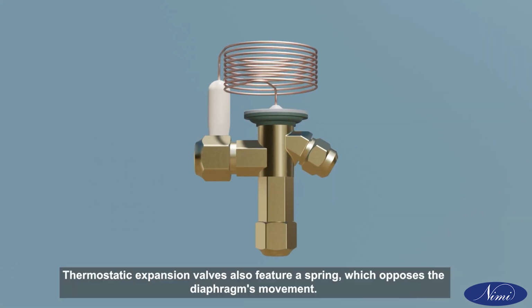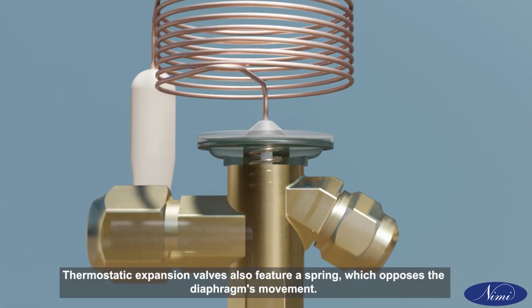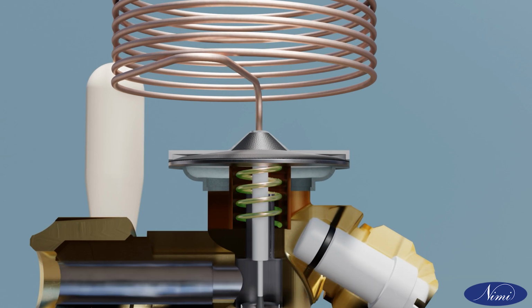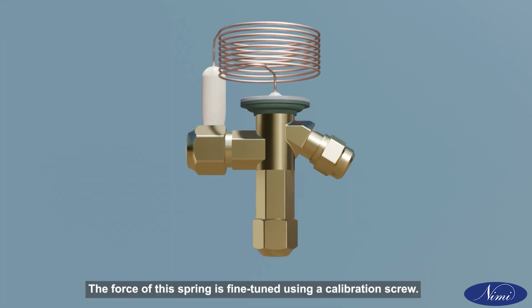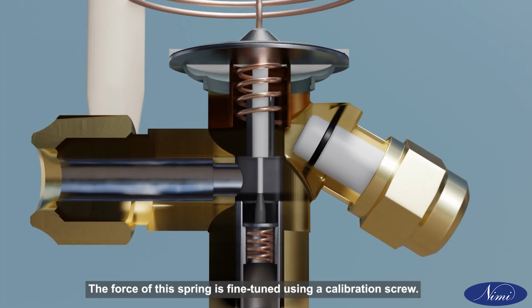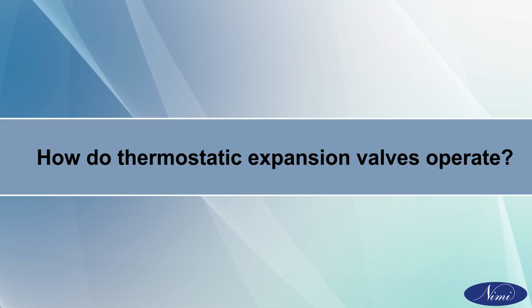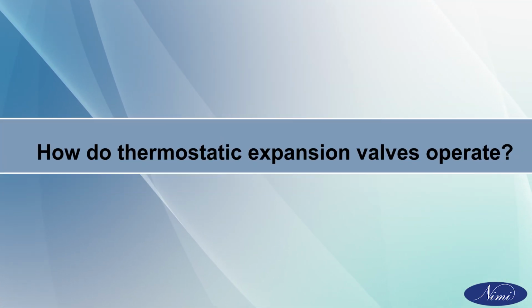Thermostatic expansion valves also feature a spring, which opposes the diaphragm's movement. The force of this spring is fine-tuned using a calibration screw. How do thermostatic expansion valves operate?